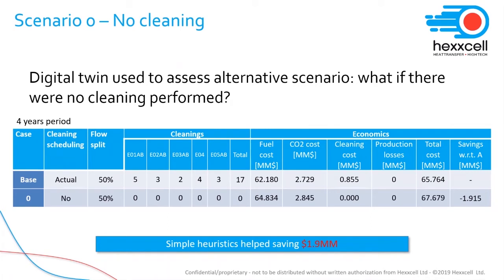This tells us how successful the cleaning actions implemented by the refinery were. As you can see from the table, the cleaning schedule implemented brought about $2 million savings over 4 years of operation over the no cleaning scenario. It is to be noted that the furnace was assumed here to be significantly over-designed. Therefore, the furnace limit was not hit even in a no cleaning scenario. This assumption allowed us to compare apples to apples and show the benefits of the various scenarios without the production losses, which would have skewed the results.